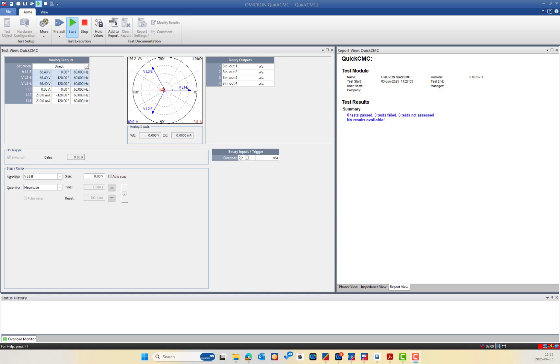Here is another solution: the C-Probe current clamp. It has different clamp ratios — 10 mV/A, equivalent to a 10 milli-ohm shunt resistor, and a higher accuracy range of 100 mV/A. I will demonstrate the difference by comparing IL2 measured with the C-Shunt 1 milli-ohm against the C-Probe at 100 mV/A.